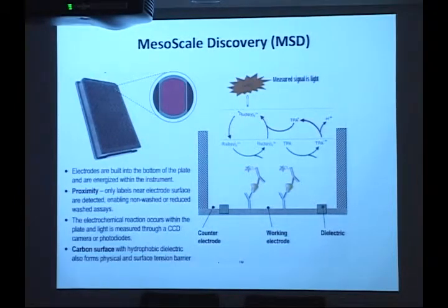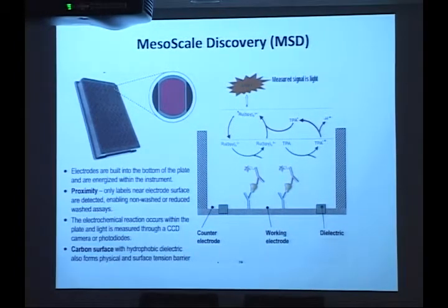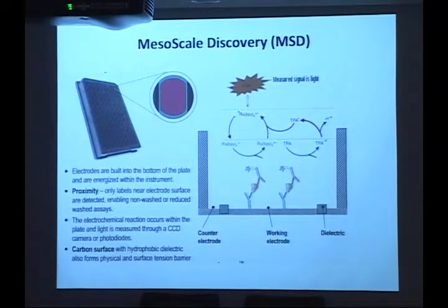The electrochemiluminescence platform for MSD uses pre-patterned arrays. So what we receive from the company is pre-patterned capture of up to 10 analytes in each well, segregated at the bottom of the well. Again, we're building this ELISA at the bottom of the well. We're activating the signal, amplifying the signal using chemicals to emit a light signal. The light that is emitted is captured by a CCD camera and later translated into intensity numbers.